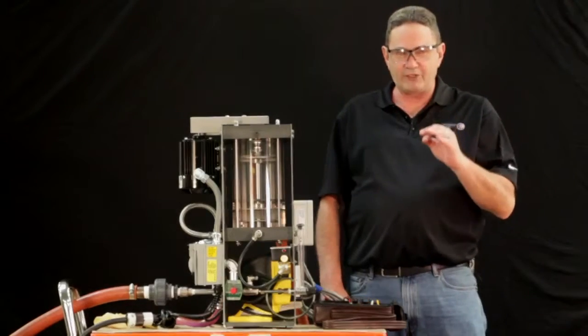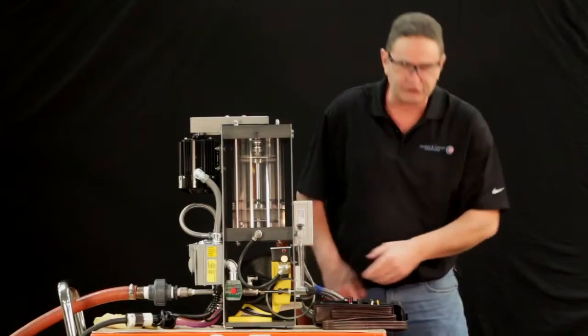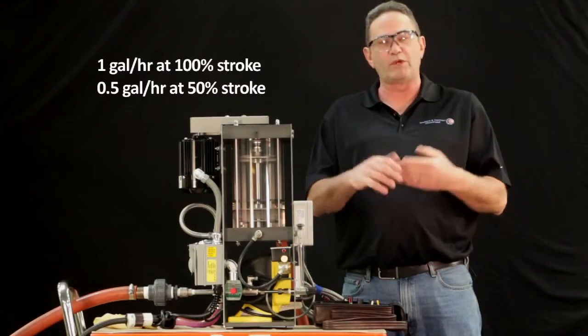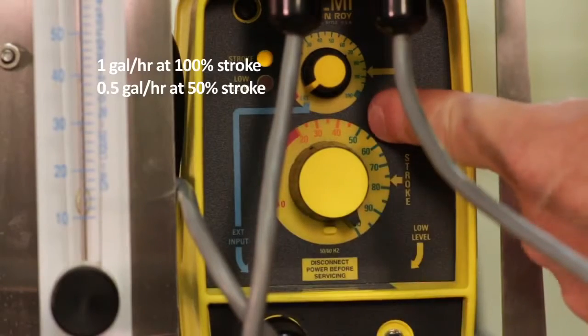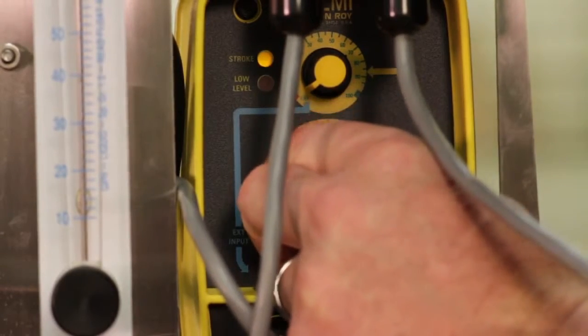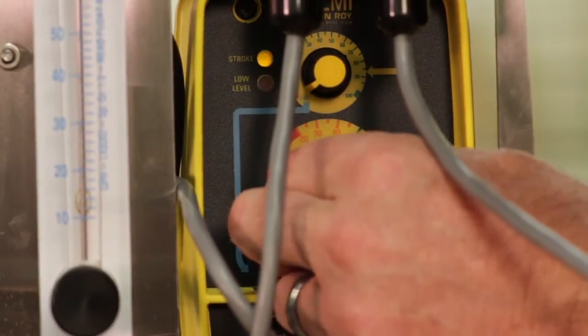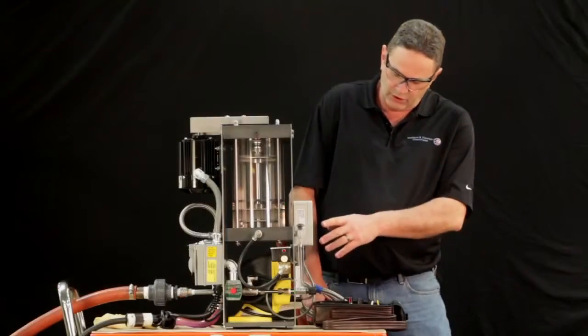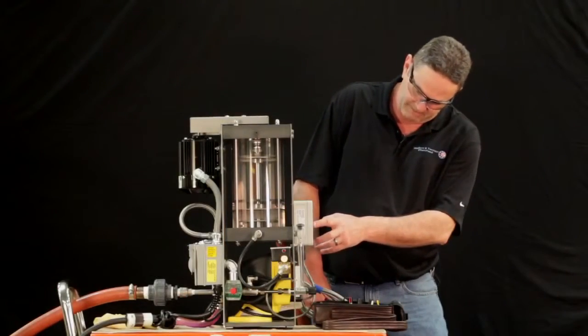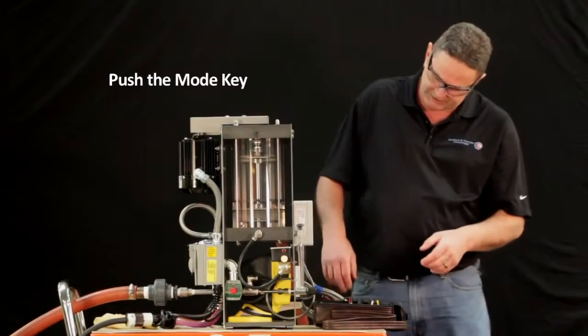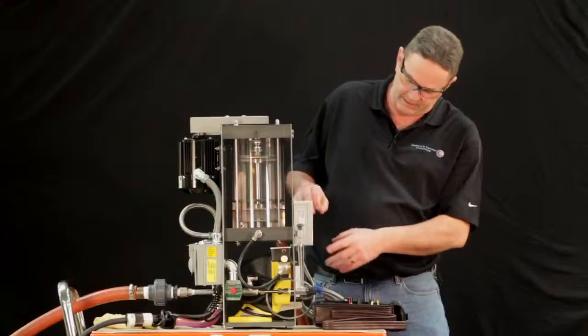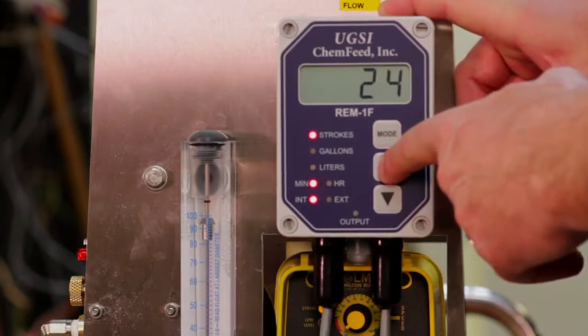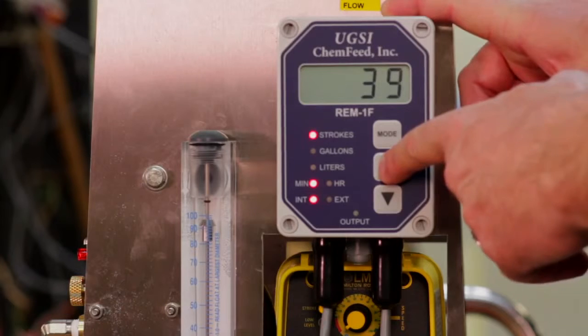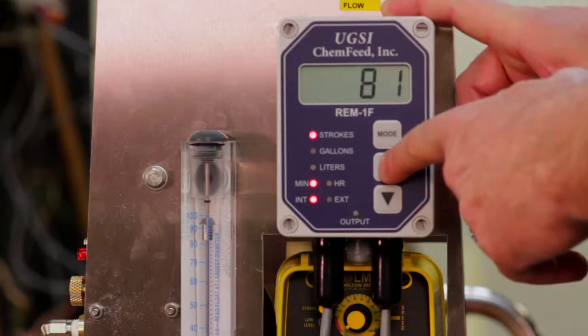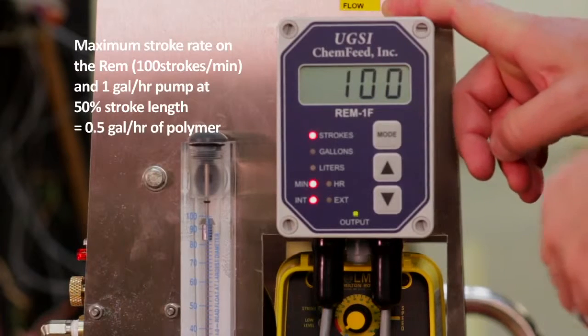When the unit is up and operational, we will make the adjustment on the stroke. This is a 1 gallon per hour pump. We are simply going to take it back to 50%. Okay, to run, we simply take the mode key, energize once. It's now set at 24 strokes per minute. To increase our strokes, we simply use the up arrow. Maximum stroke is 100.